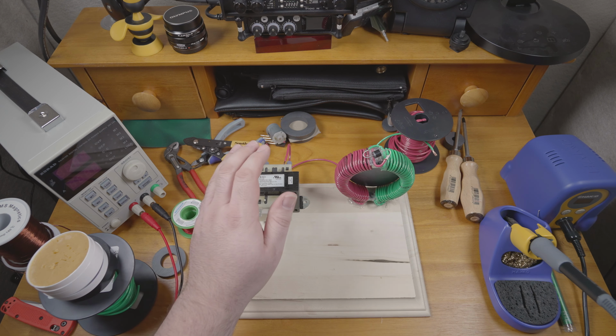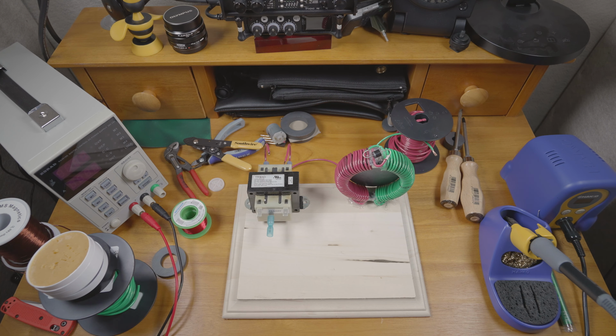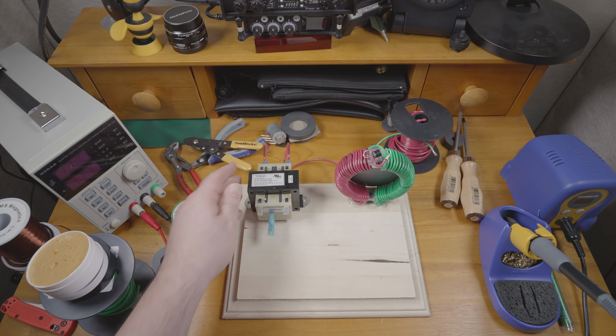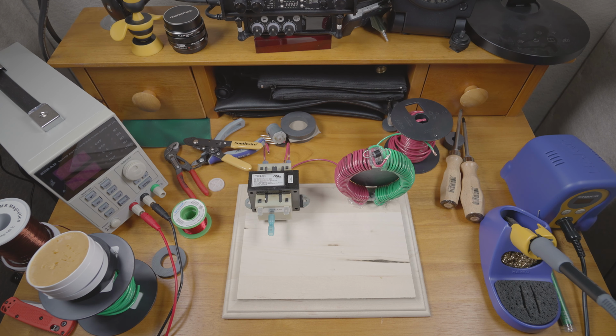And that brings us to the transformer. No surprise, but this transformer is woefully undersized considering the 10 kilowatt claim. The transformer I have here is roughly similar in size to the one in the video, and it is a 50 VA transformer. Even assuming a unity power factor, which is the best case scenario, that's still 0.5% of 10 kilowatts.